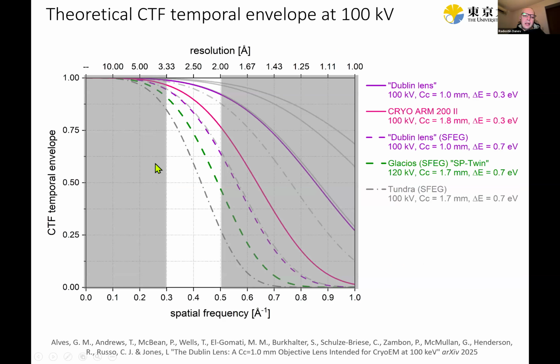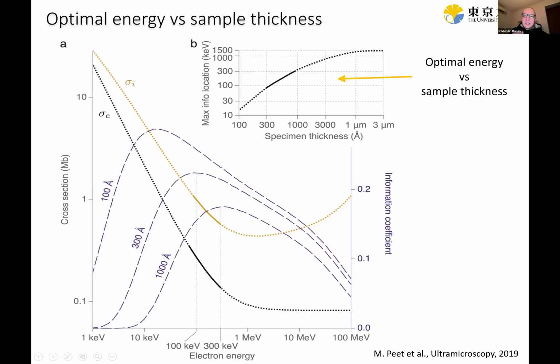Here it is shown in purple. And on the bottom here is the Tundra, which is a standard product. It is with a narrow gap, but it has a Schottky FEG source. Now, this is a very important plot we should consider. It was calculated by Matthew Peet and Chris Russo in their amazing work on measuring the inelastic and elastic scattering cross sections at various voltages, and from that they calculated the optimal accelerating voltage versus sample thickness. So here we have the sample thickness on the horizontal axis and voltage on the vertical axis. At 100 keV it's about 30 nanometers. At 200 keV it's about 50 nanometers, and then at 300 keV, of course, larger than that.